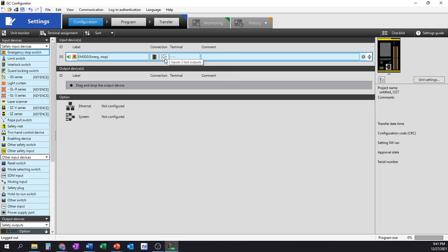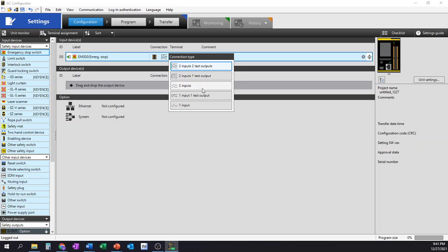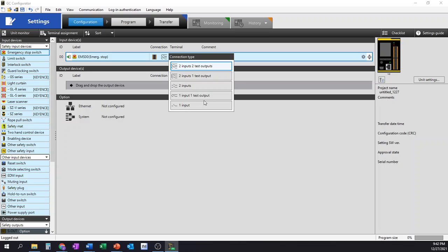From there you have the input terminals that you can decide. If you did the two inputs and the two test outputs, the controller is going to give you two dedicated outputs sending power out from the controller to your contact terminals on your push button, and then from your push button you bring those back into your two safety inputs. If that's not your standard way of wiring, you might use one dedicated power supply that runs all of your safeties, with all of that 24 volts DC positive going out to the button, and then from the button going back into the controller. The one input option, you can use that. It doesn't matter either one of these one inputs, you could use those. However, understand those are not considered on the higher end of functional safety that generally you would be required to meet. Those would be like low level safety.